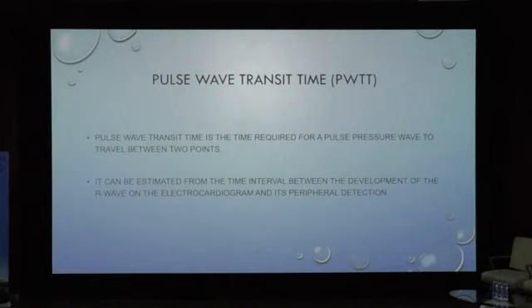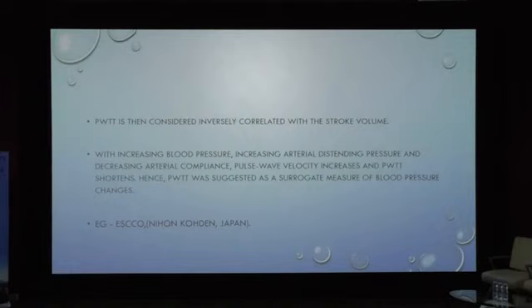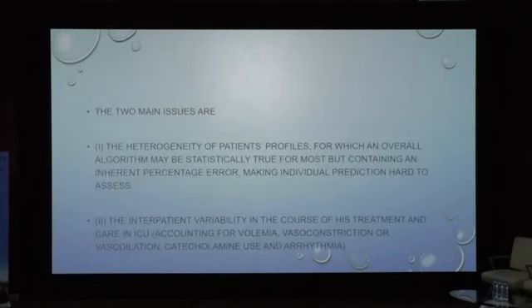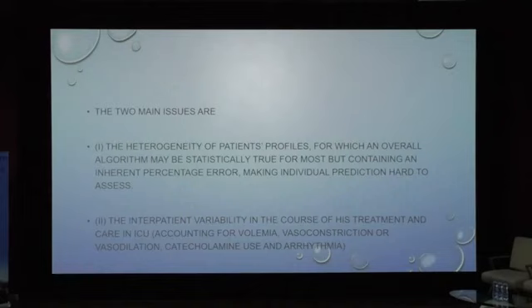Pulse wave transit time is the time required for the pulse pressure wave to travel between two points, estimated from the R-wave of the ECG to peripheral detection. It is inversely correlated to velocity and volume — with increasing blood pressure, arterial distending pressure, and compliance, pulse wave velocity increases and transit time shortens. It is suggested as a surrogate marker of blood pressure changes, used with the esCCO device. Limitations include heterogeneity of patient profiles and interpatient variability, with hypovolemia, vasoconstriction, and vasodilation all affecting results.